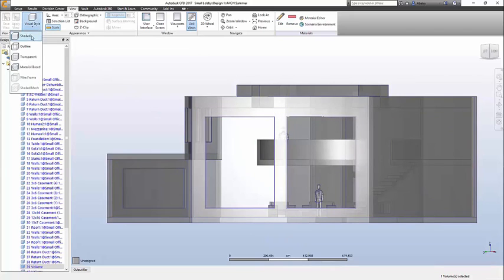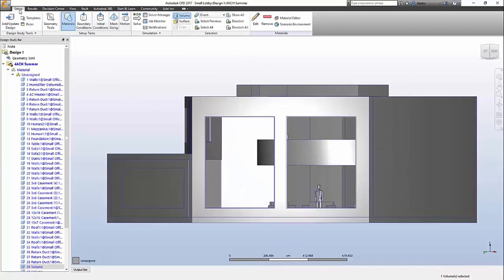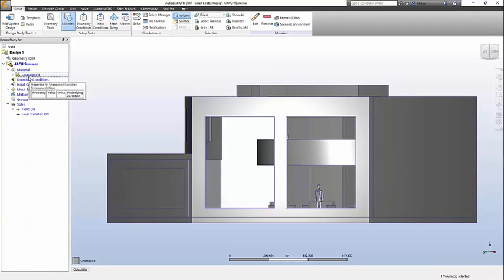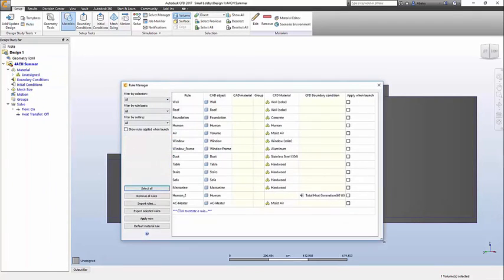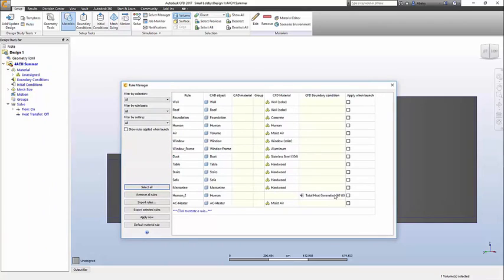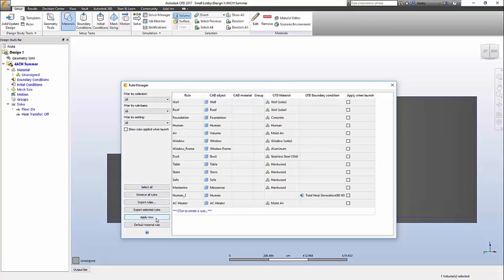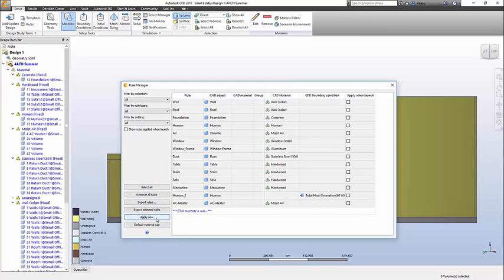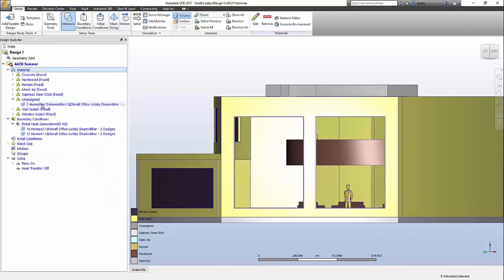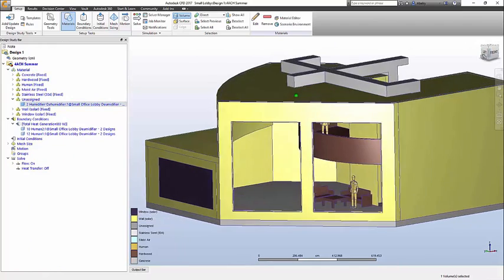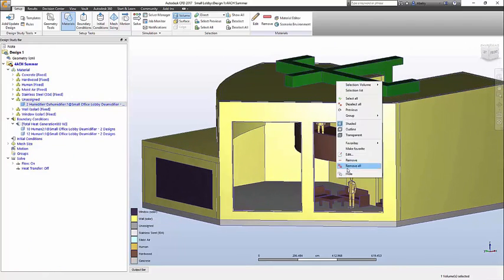The first thing you will do is use the Revit family names to automatically assign material properties. Rules automation will save you time and ensure accuracy in the setup, and can even be applied automatically during the launching process. It is important to point out that we are using moist air, which means in addition to temperature, pressure, and turbulence, we'll be tracking the relative humidity, and each person will generate 70 watts. These details are important to conform to thermal comfort standards.